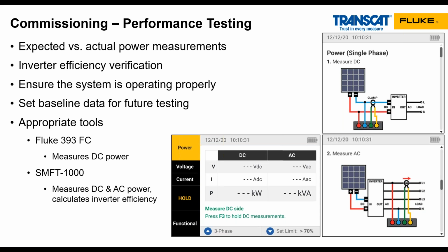The first one on the top right is measuring our DC power, so putting our voltage probes on and a current clamp around one of the DC conductors, measuring power. The SMFT will save that measurement. Then we can move our probes to the AC side, measure AC power, and it will automatically calculate our inverter efficiency. The limitations of the SMFT 1000 for this power measurement are the current clamp that comes with it is limited to 60 amps, so we can't test circuits above 60 amps.